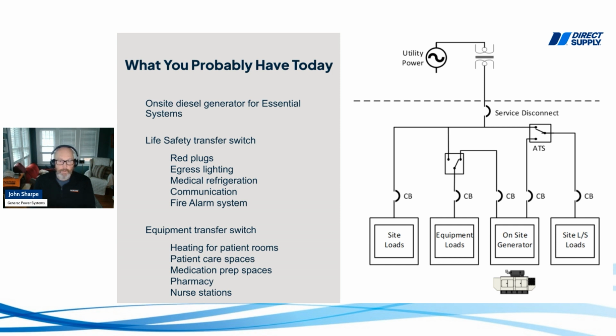Outside of red plugs, those are things you typically see in every building. Every building occupied by common people has to have fire alarm, communication, and egress lighting backed up by a life safety generator. Additionally, here we're talking about red plugs and medical refrigeration.